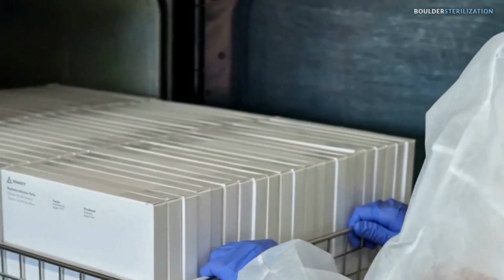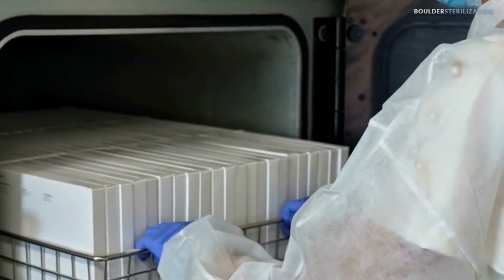Here's something most people don't realize about EO sterilization. We don't validate the cycle by designing it to kill the microorganisms that exist on your device. We design it to kill far more on purpose. It's called the overkill method. Under ISO 11135, the overkill or half cycle method is the workhorse for ethylene oxide.